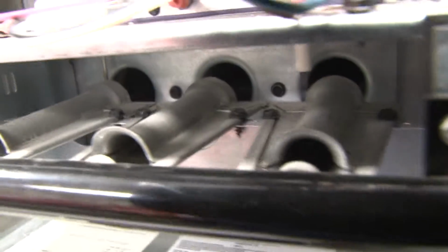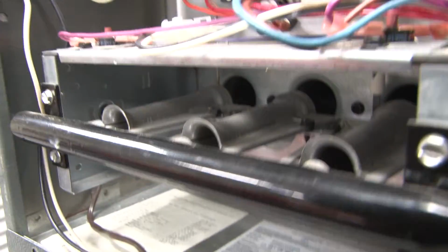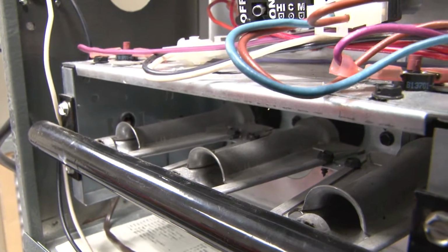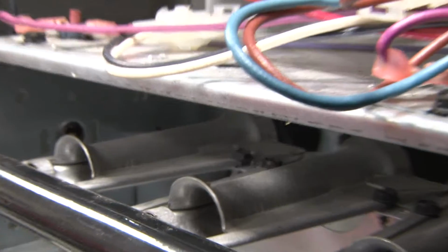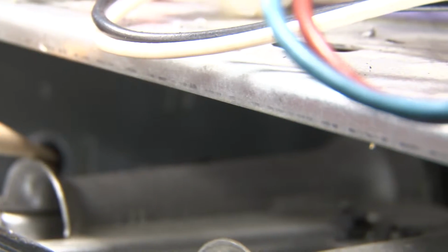This burner is basically a Venturi type burner, where you can zoom in a little bit so you could probably see a little bit better. The construction of this burner, it starts out very large at the opening, and it will reduce down to cause a restriction, and any restriction in airflow will cause the velocity to increase.